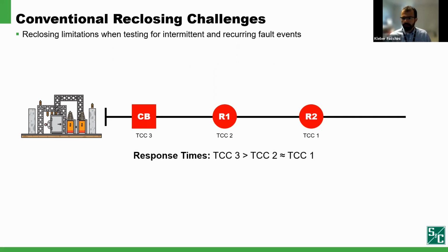After some given time, the fault recurs, as system voltage is present in the circuit and the fault path is recarbonized. R1 and R2 will trip, and as they trip, they will go through their reclosing sequence again to test for fault presence and close once the fault is no longer detectable. As the fault path recarbonizes and therefore becomes detectable again, the reclosers will trip again and start their reclosing sequence.